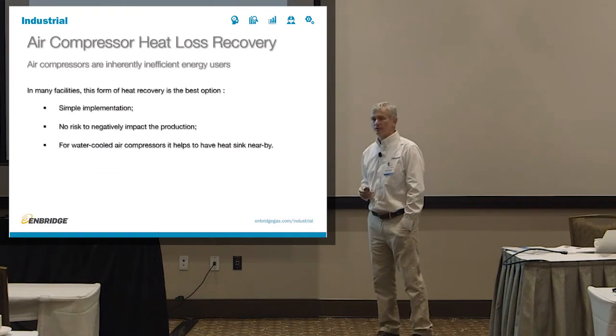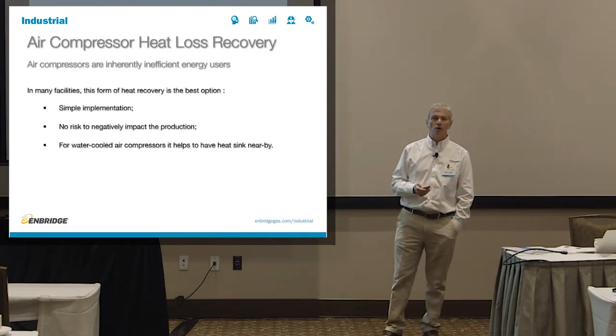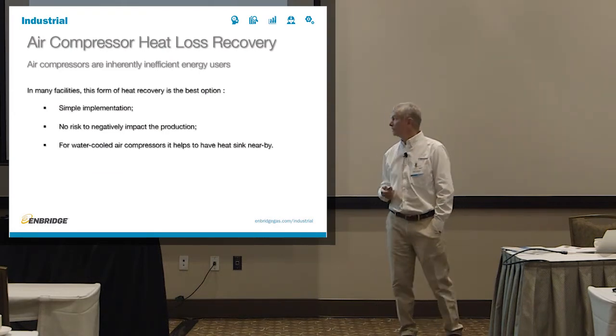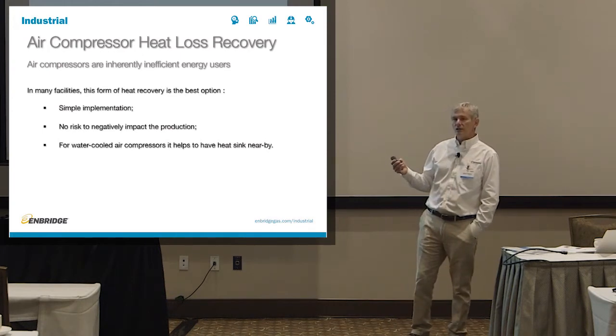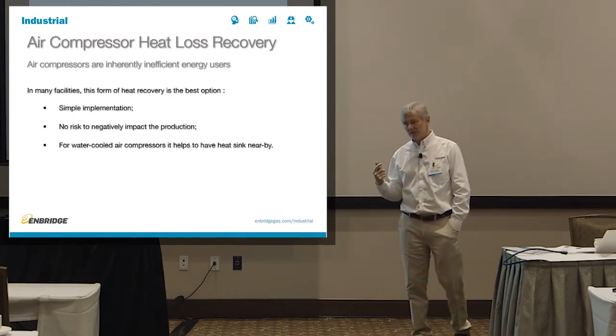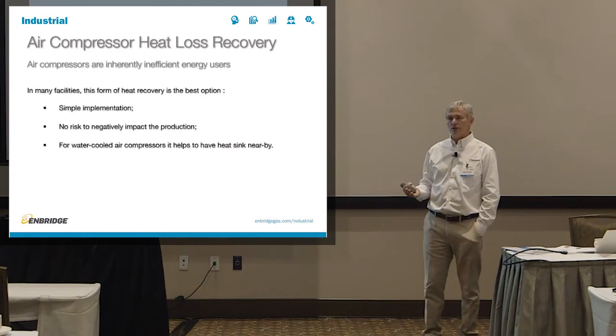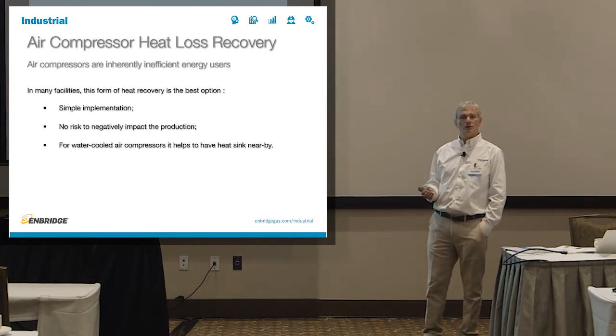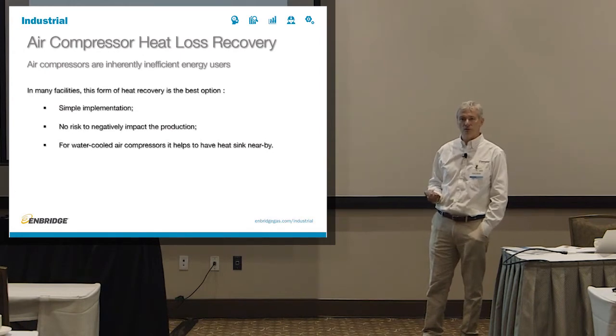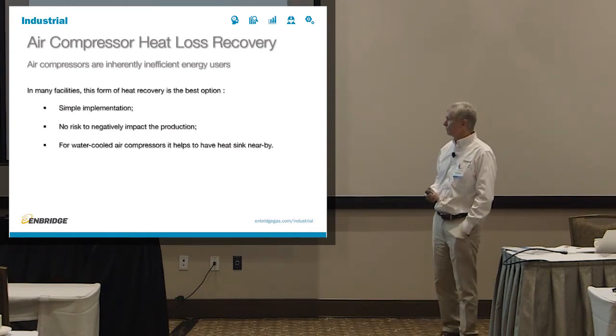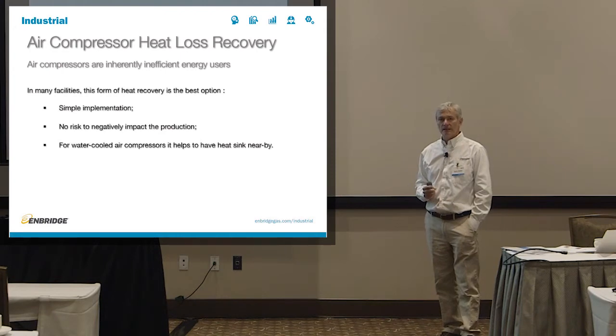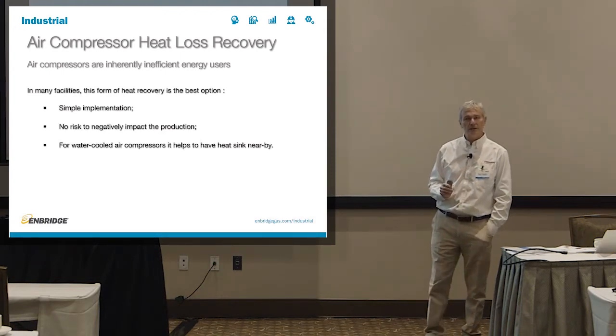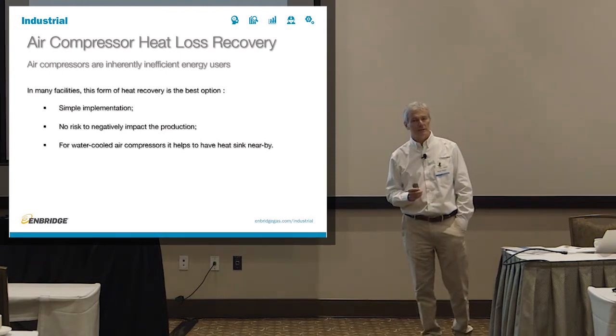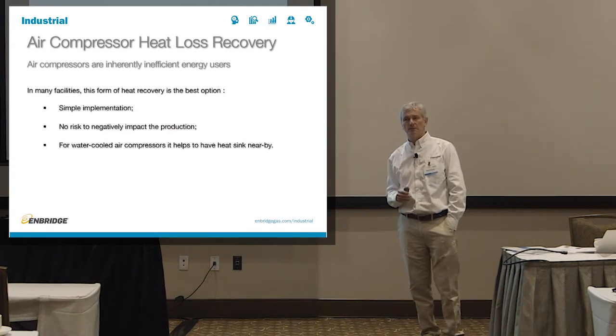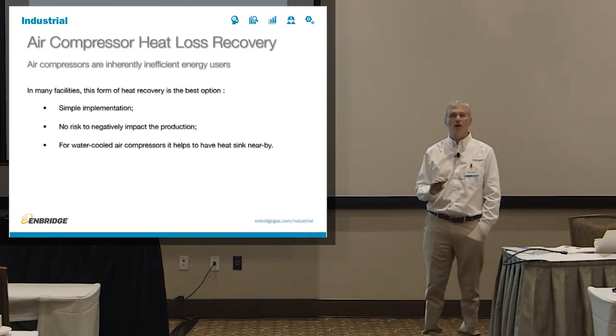So what can you do about it? How can you recover heat off the compressor? Usually in a very, very simple way, and I'll show you a couple of examples later on. There is no risk of negatively affecting production because the compressor is already wasting that heat anyway. You don't have to do anything for it to waste heat. It just sits there. For water-cooled air compressors, it does help your payback if the heat sink is close by. It's not always necessary, but it helps because you avoid building a long piping system.